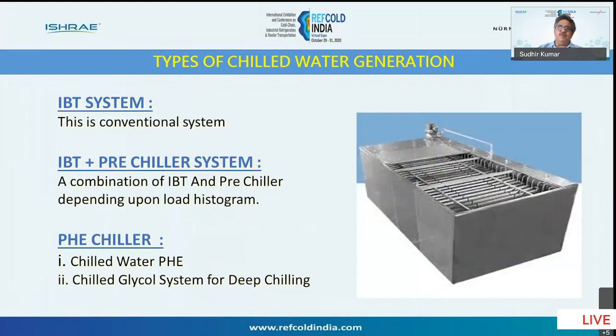Then after some time, they found that ice bank tank was not energy efficient because it was running at a lower suction temperature. So people started designing an IBT plus pre-chiller system. So basically, there will be an IBT, but the peak load is cooled by the pre-chiller system. Say, for example, after cooling the milk in the process area, the water gets heated up. It comes at say 11 degrees or 12 degrees. Once the 11 degree, 12 degree water passes through a pre-chiller, it is cooled to 4 degrees. Then the 4 degree water goes into the IBT system. So in this way, you can reduce the size of the IBT and use a PHE for the pre-chiller system. Instead of PHE, people are now also using falling film chiller.